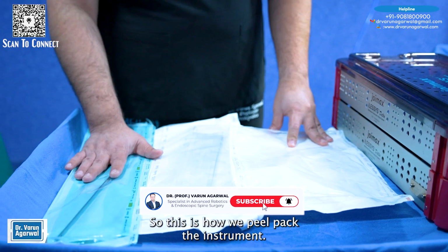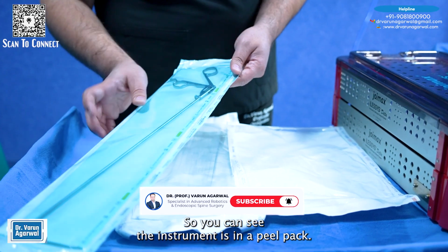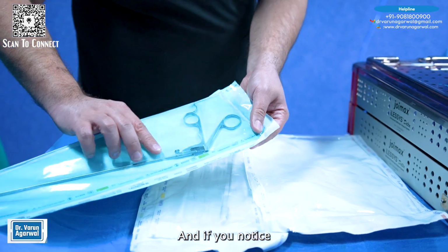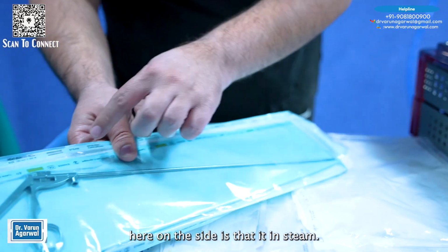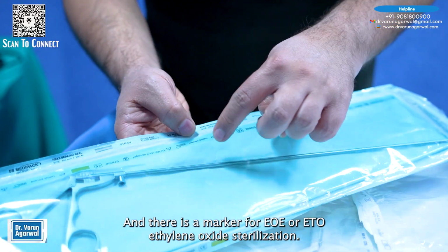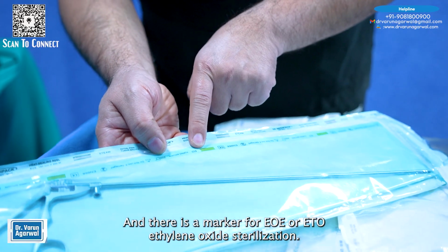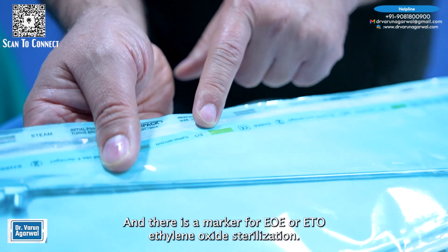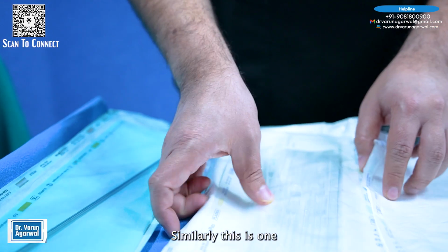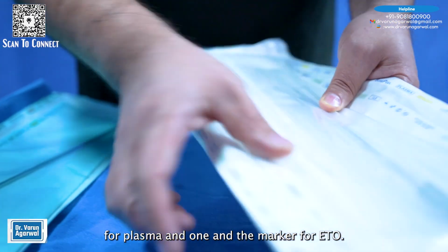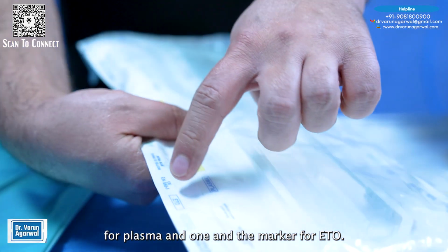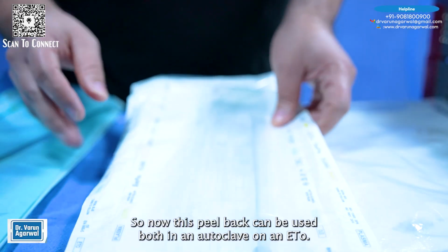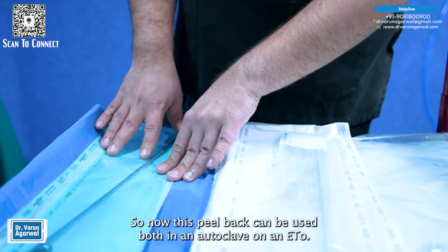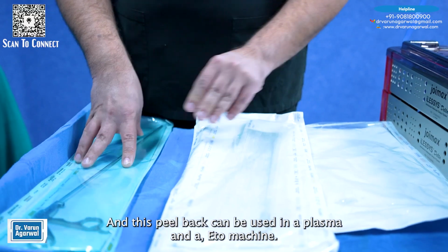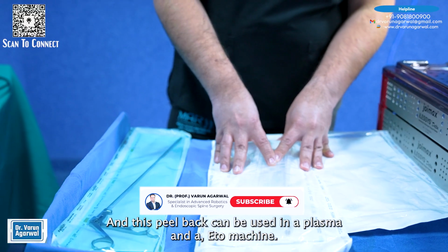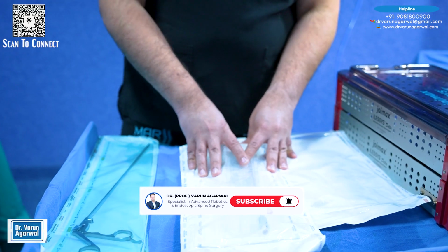So this is how we peel pack the instruments. You can see the instrument is in a peel pack, and if you notice, here on the side is written steam, and there is a marker for EO or ETO, ethylene oxide sterilization. Similarly, this is one for plasma and the marker for ETO. So now this peel pack can be used both in an autoclave or an ETO, and this peel pack can be used in a plasma and an ETO machine.